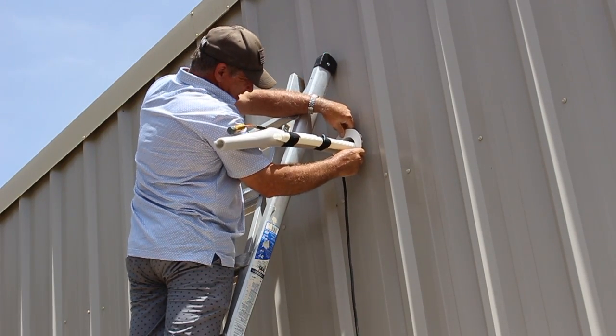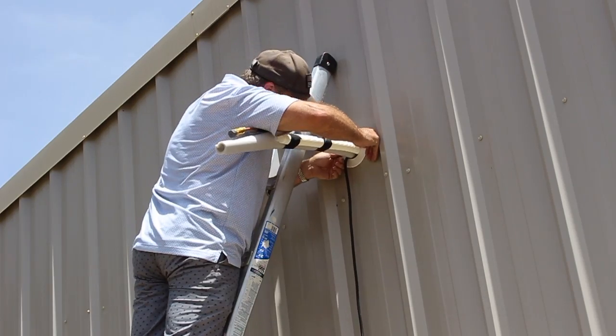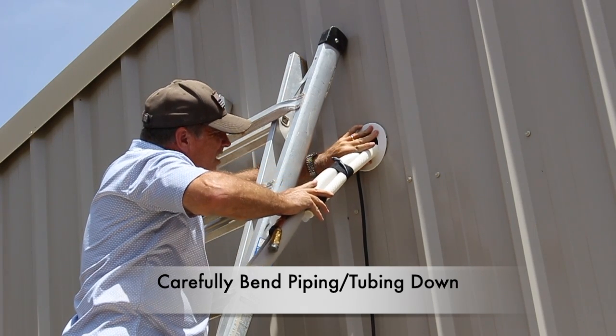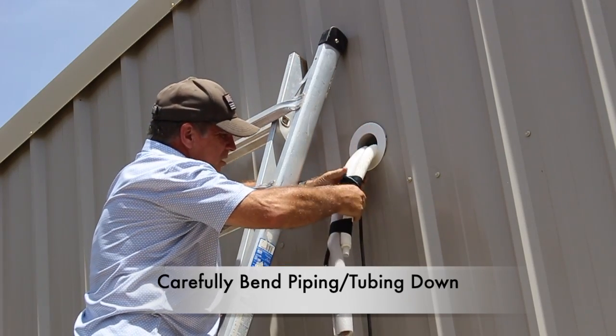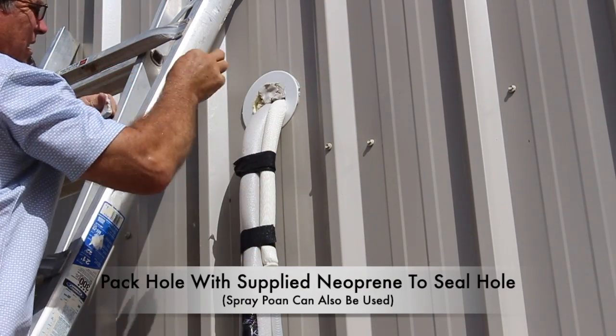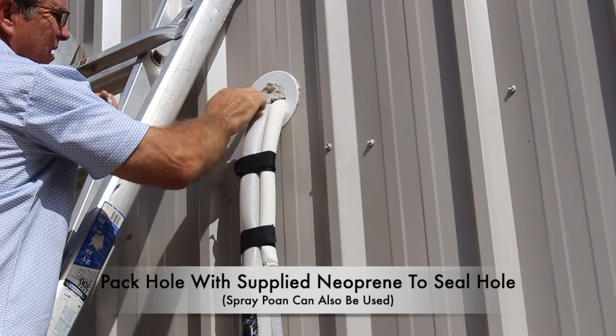I decided to mount the condenser to a concrete pad to prevent any sound or vibrations coming through the building with a wall mount. Now I can go ahead and install the finishing ring cap on the exterior wall. It is very important that I bend the line set piping and tubing in a downward motion so that I do not kink any of the lines. Go ahead and pack the hole with supplied neoprene — you can also use spray foam. This will cover the hole to prevent any air from escaping or anything from entering the building.